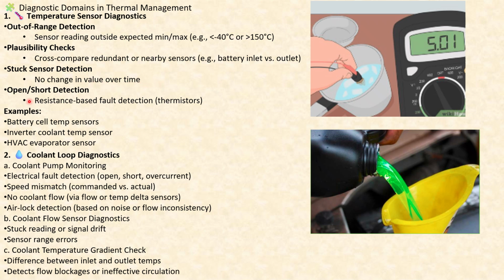Now, when it comes to open and short detection, resistance based fault detection of thermistors. All right. So, for example, battery cell temperature sensors, inverter coolant temperature sensor, HVAC evaporator sensor. These are all the various kinds of sensors that fall under the category of temperature sensor diagnostics.